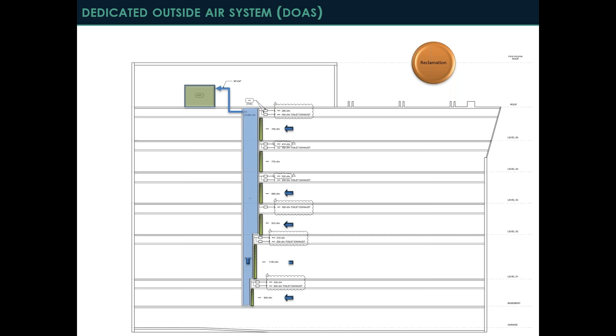Given this building sits right on Florida Avenue, and during the morning and afternoon it can be gridlocked with traffic, we expect the building will have better air quality by recirculating than by taking in outside air for a fair amount of the time. Because the outside air in Washington, D.C. is very hot and humid, it takes a tremendous amount of energy to dehumidify and cool it. So with a system like this, we don't have to use all that energy for outside air, and the occupants end up with a better quality airstream and better health attributes as a result.